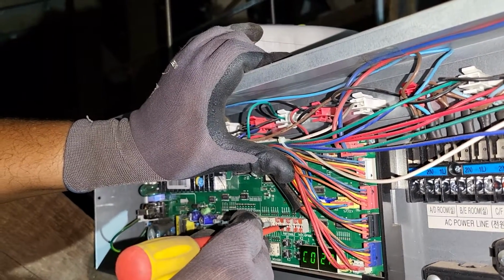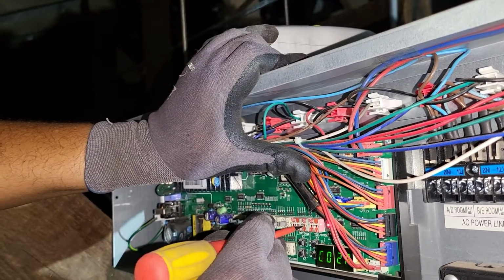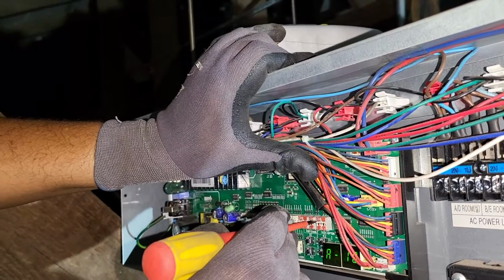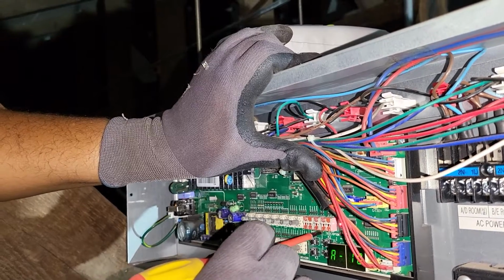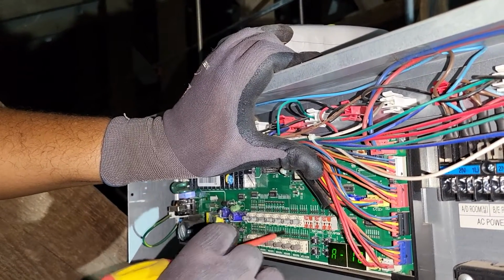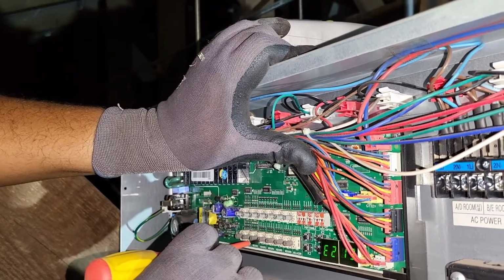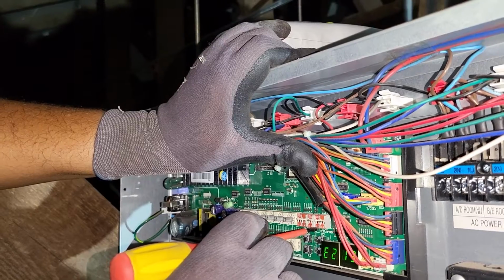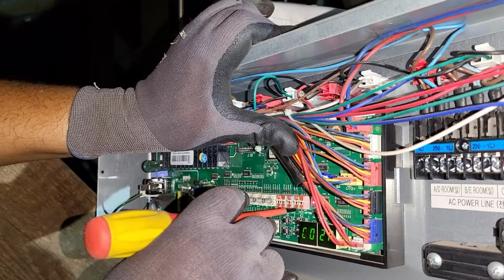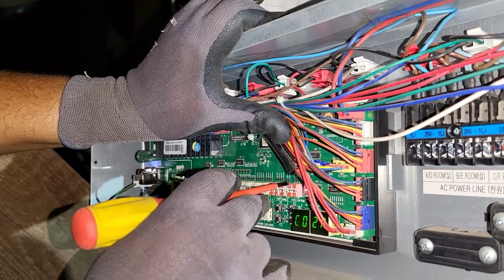So circuit 1, sorry, that's the wrong one. That's not the SW switch, this is the SW switch. Number 1 would be for circuit A/D, number 2 would be for circuit B/E, number 3 would be for circuits C/F. Because the first 4, which is 1 and 2, are running dual circuits into one set of piping, they both have to be in an off position. There's our first issue. Let's move on.